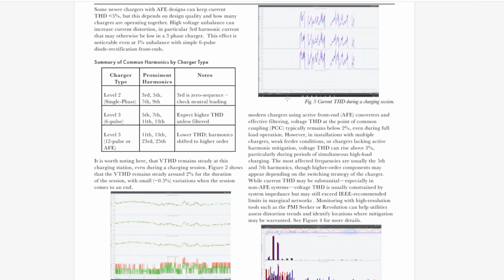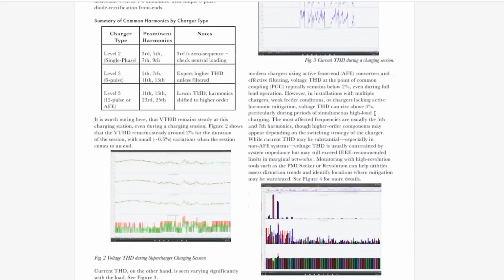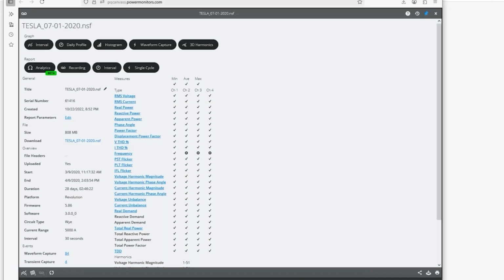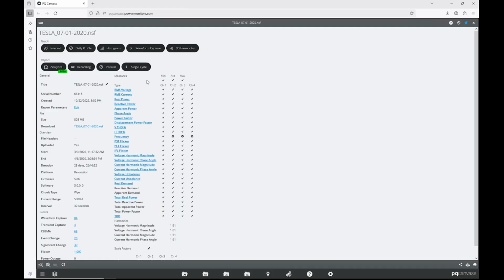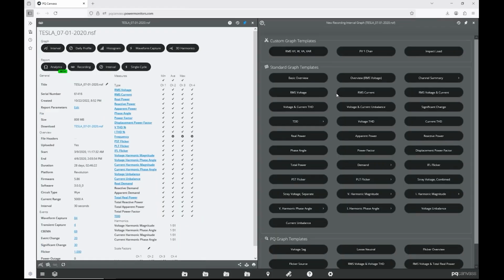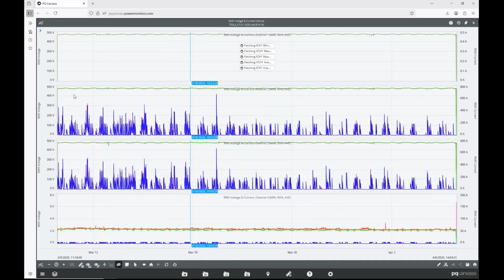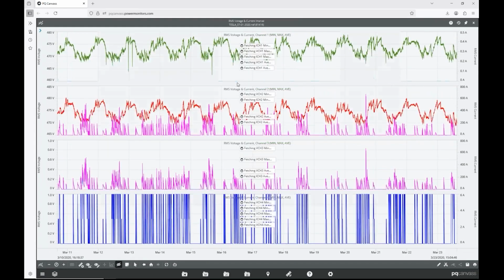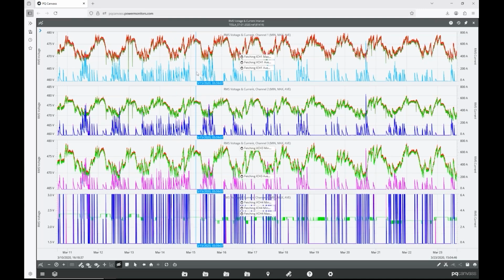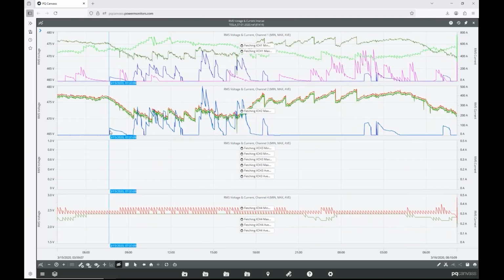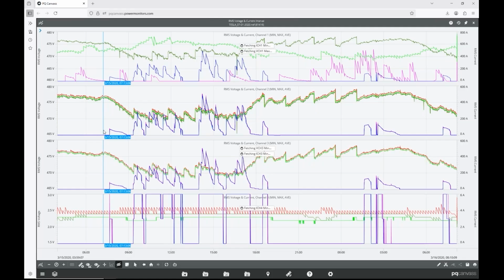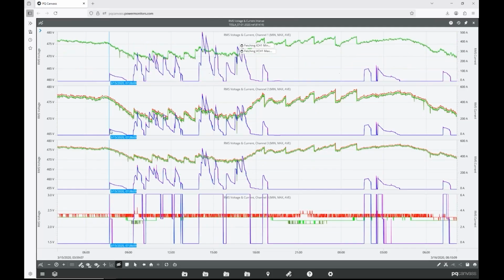Here we have some examples in the white paper of the current THD, voltage THD. And I'm going to pull up PQ Canvas so we can just see this directly. This is the Tesla supercharger. And if we just start with the interval for voltage and current, we have many days of charging. And if you zoom in, you can see the load pattern. When cars pull in, they start charging. And that's usually a step increase in current. Here at this point there were no cars plugged in, and then one car plugged in. And it starts at the highest power and then gradually tapers off. So from that standpoint, it's a friendly load because it doesn't cycle that high power off and on rapidly as the charge tapers. It gradually reduces the current.